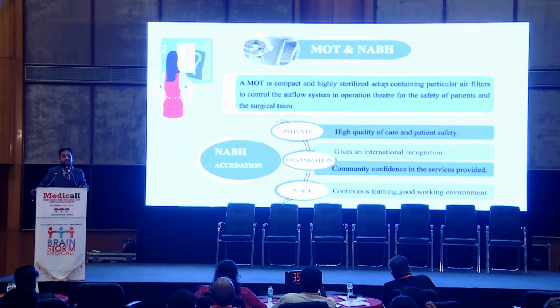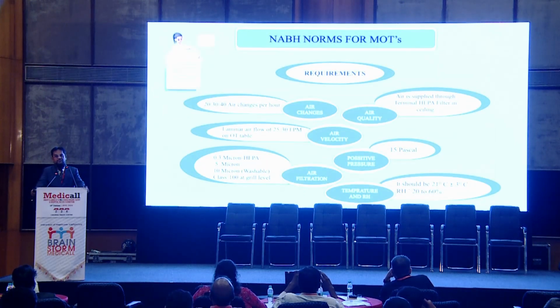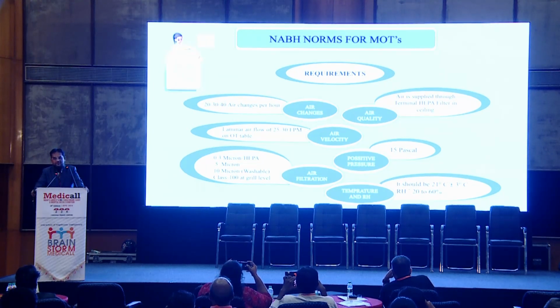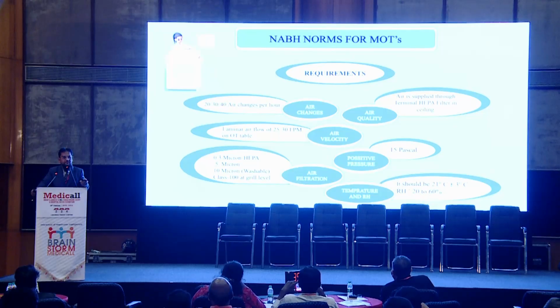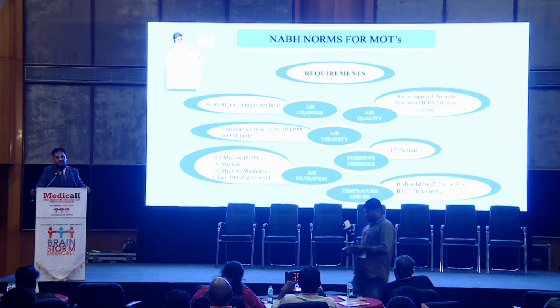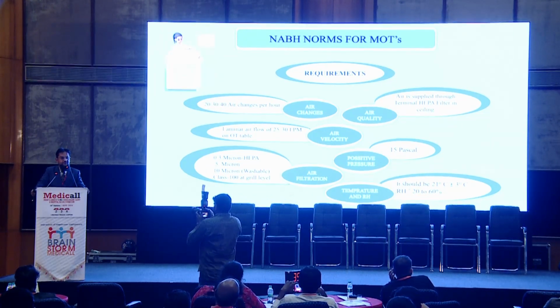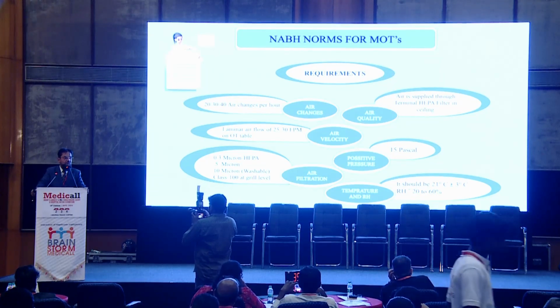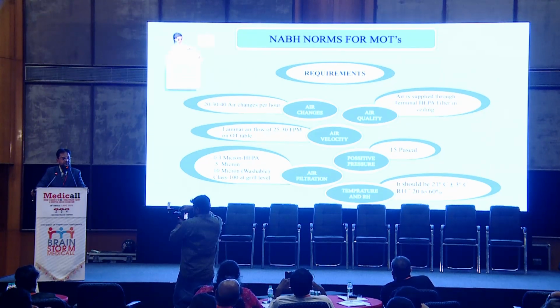You know the importance of NABH and how to go with NABH, the importance and benefits to your patients, your organization, and the staff. I will talk about what exactly is given in the requirements in the NABH guideline. They said that a minimum of 20 air changes has to be maintained. Our system will not give only 20 air changes. You can have 20, 25, 30, or 20, 30, 45, whatever you want. We can give accordingly. We have given a VFD, a variable frequency drive, so you can control the fan speed, and according to that you can maintain the air changes in your operation theaters.